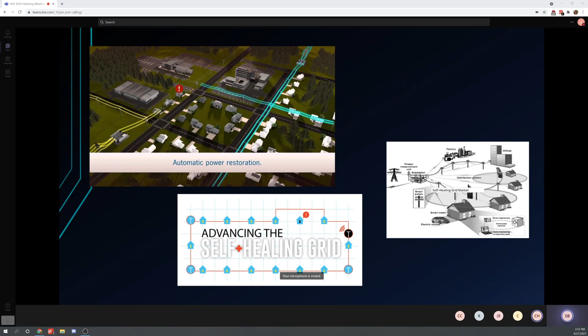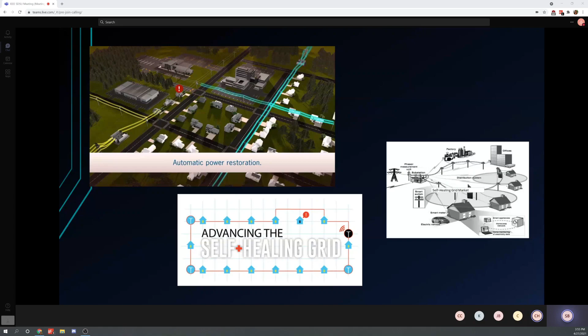We have what we call the self-healing grid, with devices out on the system that automatically sense what's going on. They can turn it on or off. Say a branch falls across a line - it's going to burn up and won't be there anymore. In the old days, that would trip power off and we'd have to go patrol the entire area to see what happened, and we might not even find it if it was something like a bird or a branch caught between the lines. Now you're talking hours and hours of people out of power, when you could just check if there's still an issue on the system.